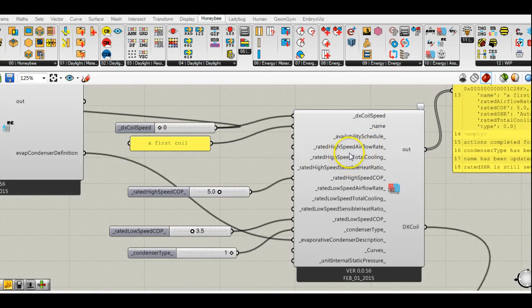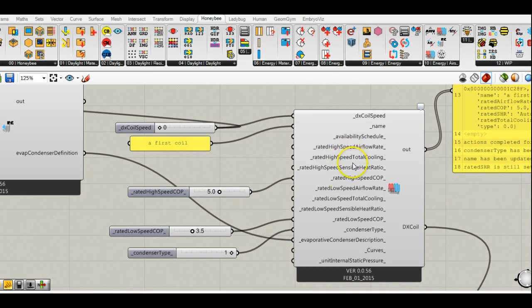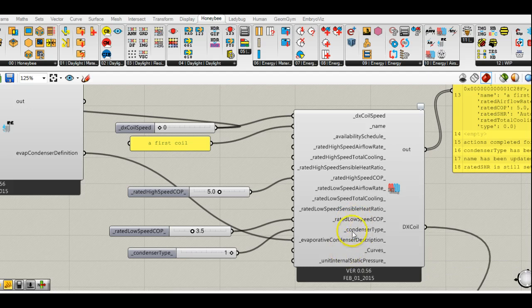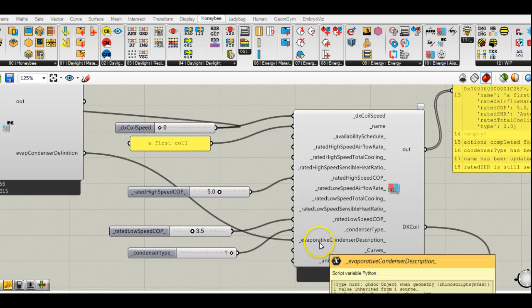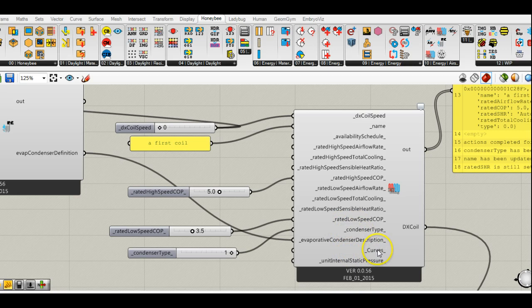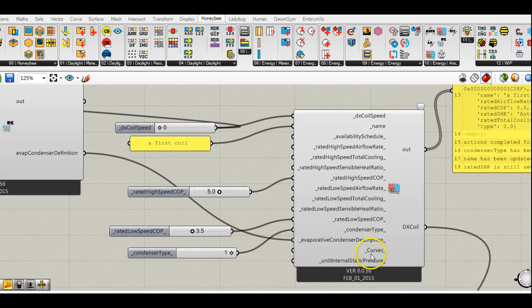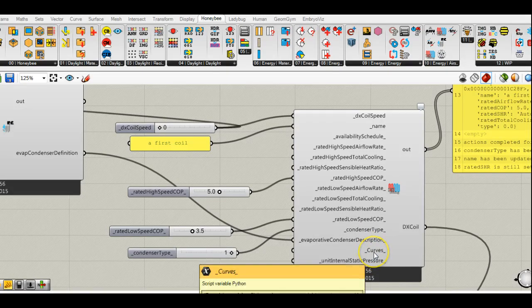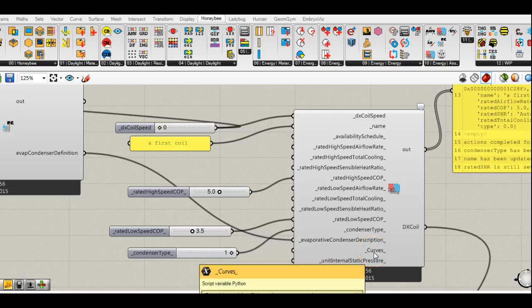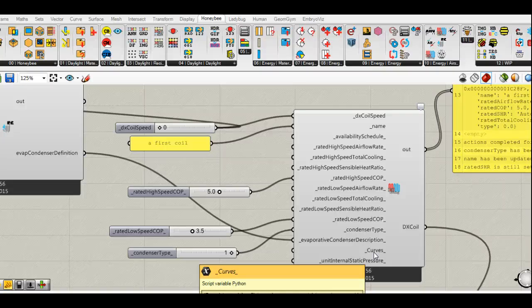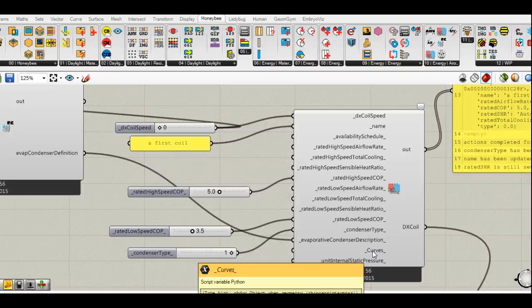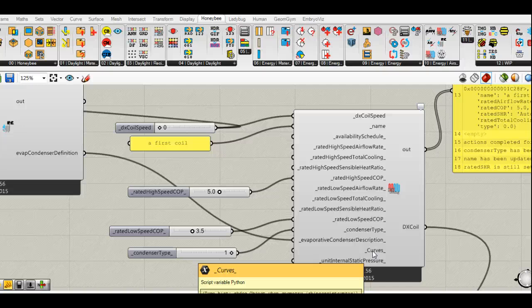And then you'll see that you've got high speed, a bunch of high speed settings and low speed settings. And then you have a condenser type and evaporative condenser. I talked about being able to make changes to the condenser and that's what you do here. And then you've got two things, curves and unit internal static pressure. These last two actually are not currently active. So if you put values in there, they're just going to be ignored. Curves would be great. I think engineers know why curves are important, but the concept is that every piece of equipment performs differently, depending upon the temperatures that it's handling and how hard it's working, basically. And so every piece of equipment performs a little differently. Most people never change these curves. It's something we'd like to do, but we haven't gotten to it yet.